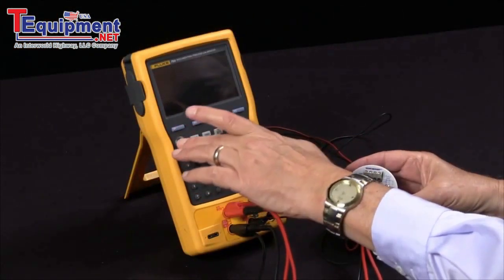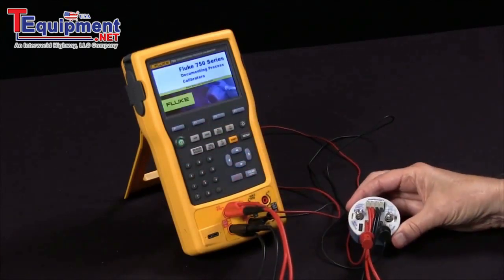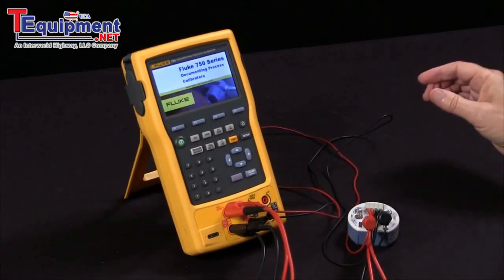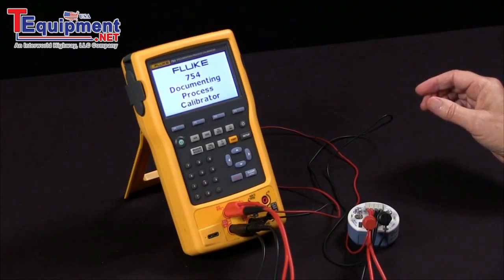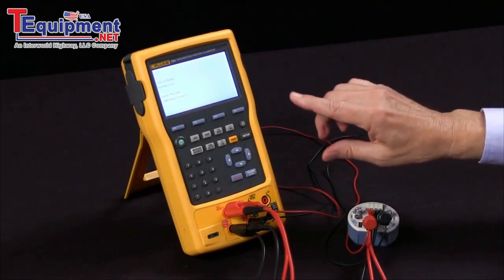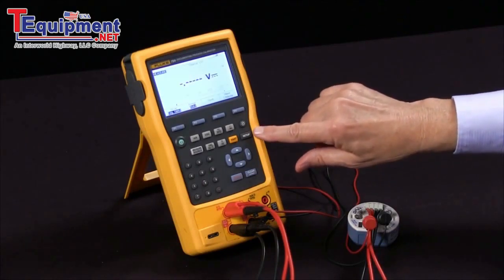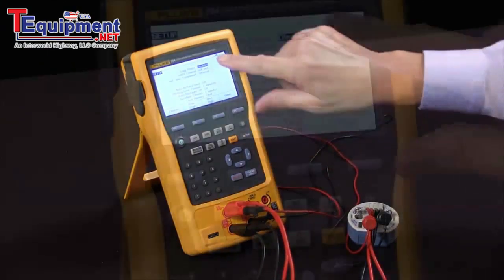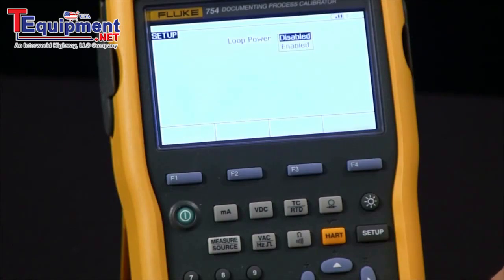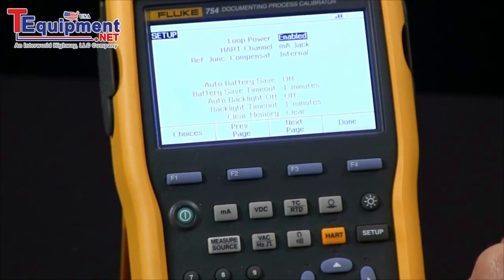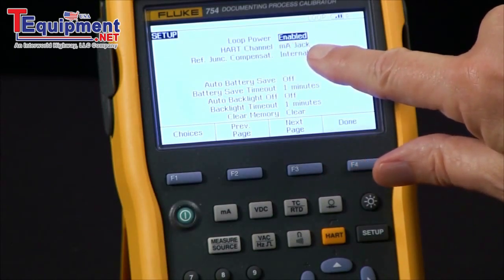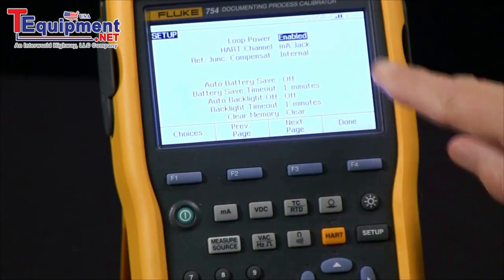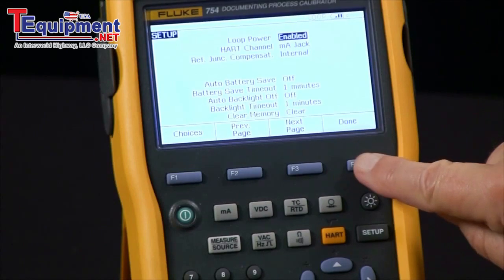I'll turn the unit on and we'll first go to setup and enable loop power. Right now it's disabled, so I'm going to enable the 24 volt loop power. You'll also notice the HART channel communication is set up via the milliamp jack, so that'll work fine for our setup.